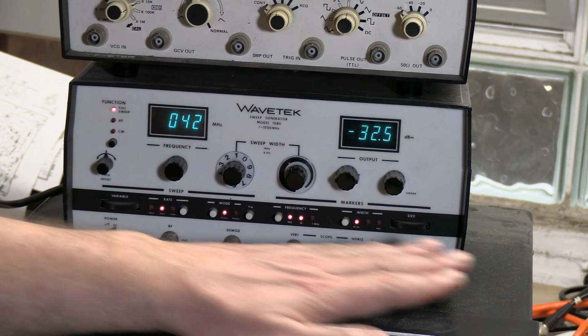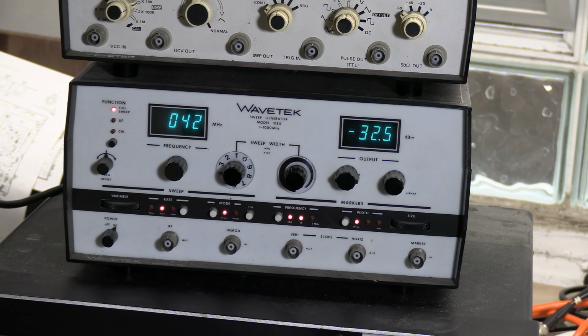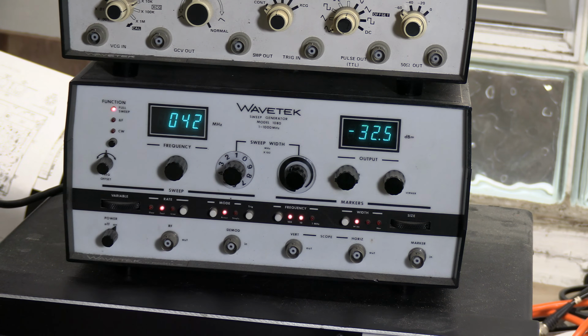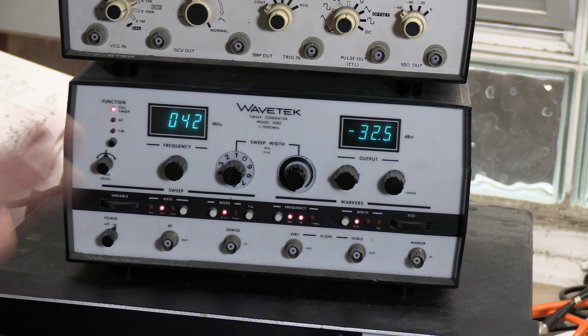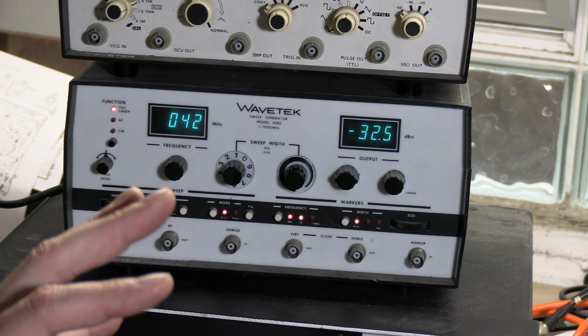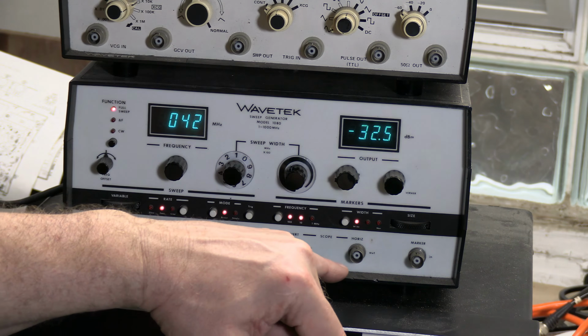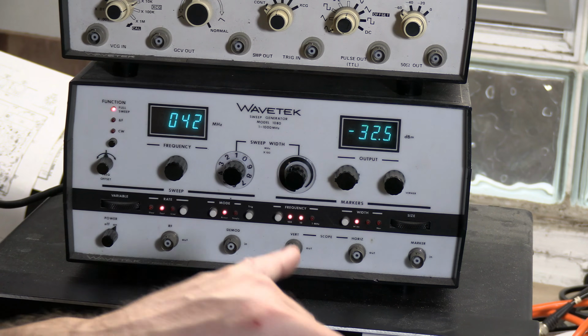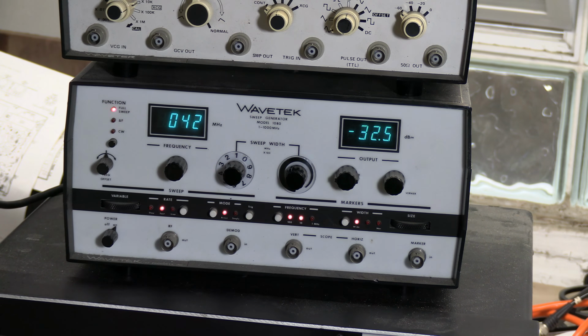And same deal with the markers as this is the 1002, where you get markers at 1, 10, and 100, and that's it. There are typically very particular frequencies for your device, like 25.75 megahertz. You want a marker there. You can't do it with these. What you need to do is have a separate RF generator and feed that in. All these devices have external marker inputs.